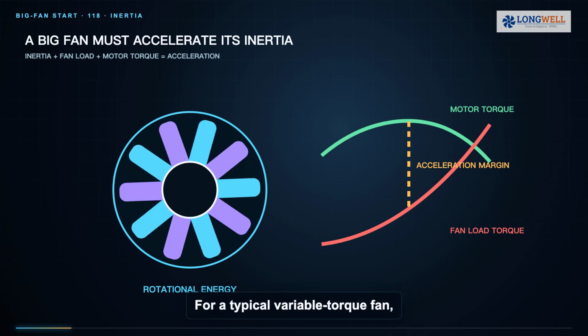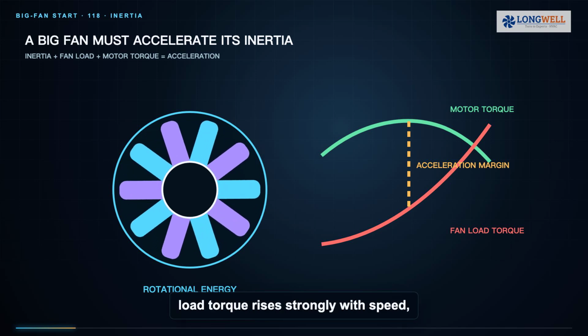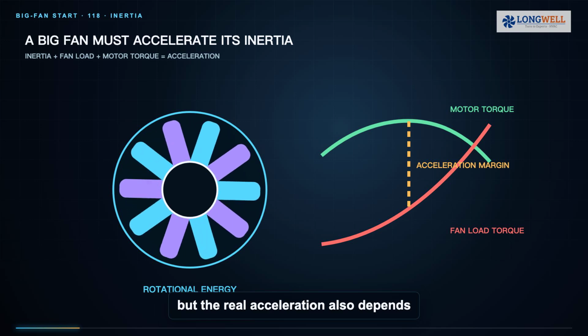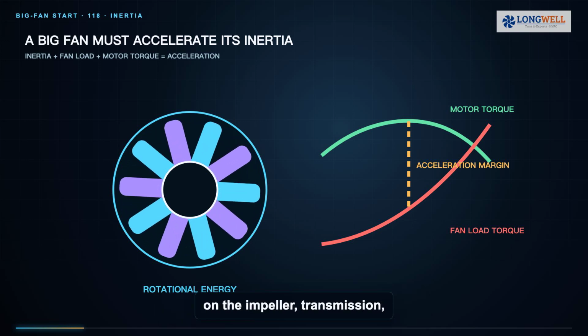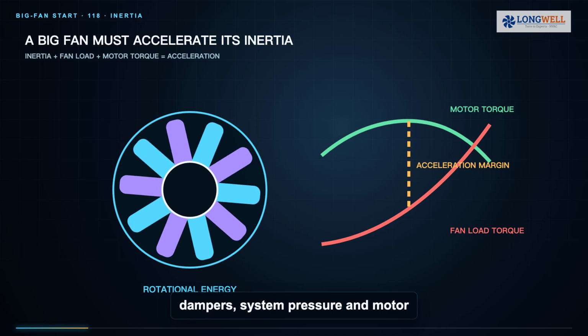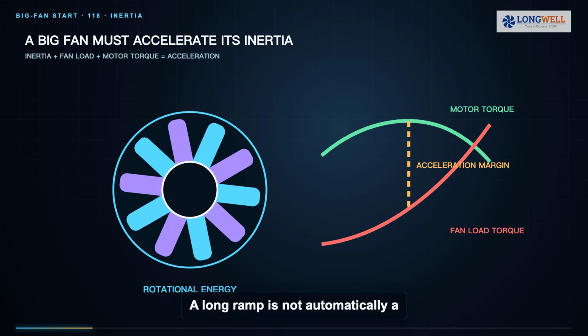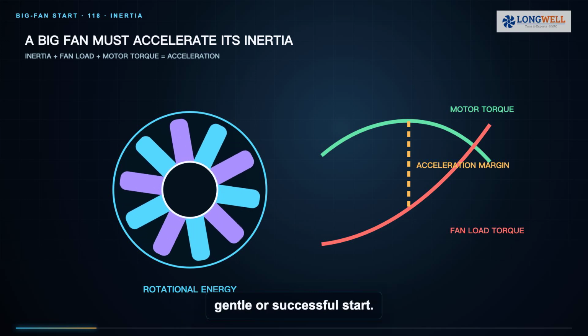For a typical variable torque fan, load torque rises strongly with speed, but the real acceleration also depends on the impeller, transmission, dampers, system pressure, and motor curve. A long ramp is not automatically a gentle or successful start.